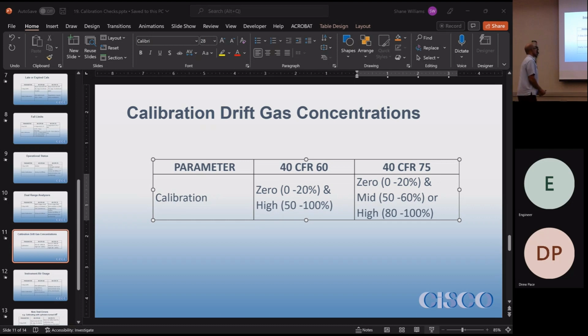And then instrument error, Part 60 doesn't address it. And I've looked in the determinations, and the determinations are basically power plants write different agencies and they say, can we do this X, Y, and Z? And the EPA responds, yeah, we'll accept that you do this X, Y, and Z. Or they'll say, no, because we don't believe it meets the technical requirements, kind of like what Charlie was saying yesterday when we were talking about the Coriolis stuff and using NIST traceability stuff.